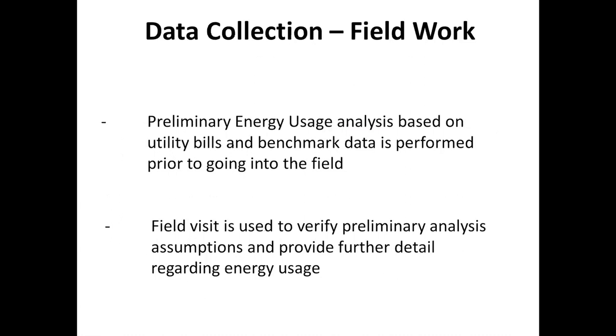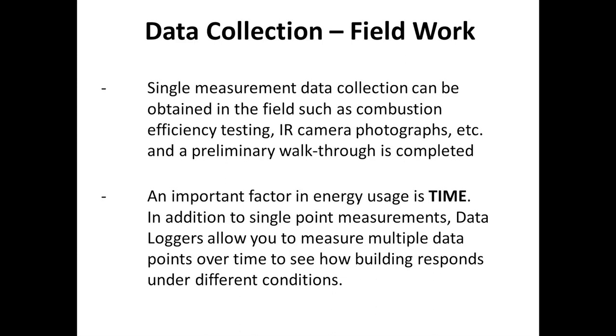So to take the preliminary energy use analysis one step further, we know what to look for. We identified that there may be some control issues. We see what the heating and cooling issues are in the building and what's expected of the building. We know the capacity is probably okay because cooling degree days and heating degree days peak at the right times with energy consumption. And now we can go on the field visit, limit our scope and really focus on some issues within the building. It's great to go in and take single measurements, such as combustion efficiency testing, taking shots with the infrared camera to look at insulation issues and how thorough insulation is in the building, and doing a preliminary walkthrough.